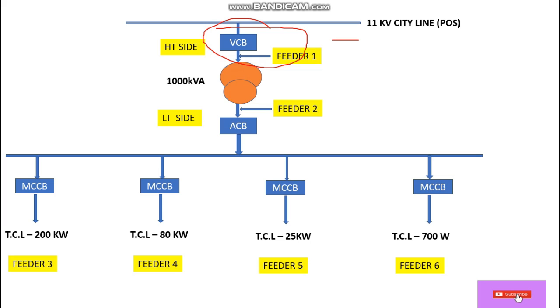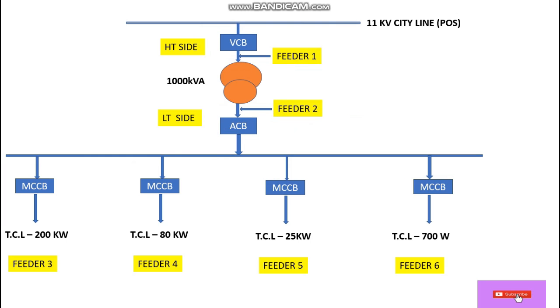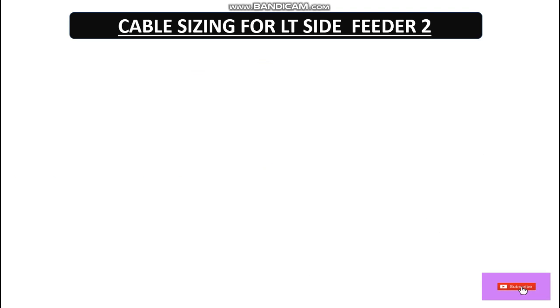This is the single line diagram. The HT cable size we have already calculated. Now we are going to calculate the cable size for the LT side, meaning the secondary side of the transformer to the breaker — the ACB — and then from the ACB to the LT panel. This is feeder one, and here is feeder two. We are going to calculate the cable size for feeder two.